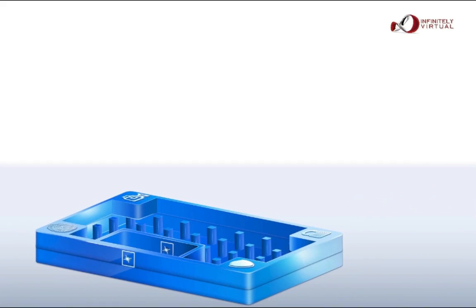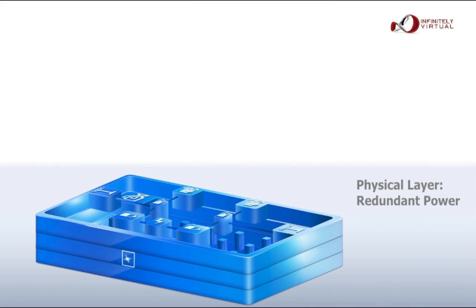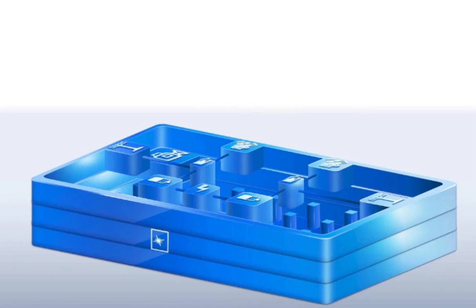On the third layer, we have 100% uptime power protection. EVE is redundantly powered and backed up by both uninterruptible power supplies and generator power. All loads, including the cooling system, are powered by an A and B circuit, each of which is robust enough to supply power for the entire load. Circuits follow a diverse path to distinct circuit breaker panels powered by diverse UPS systems, utility power, and generators — each connected to automatic transfer switches — designed to ensure 100% system uptime by eliminating any single points of failure.